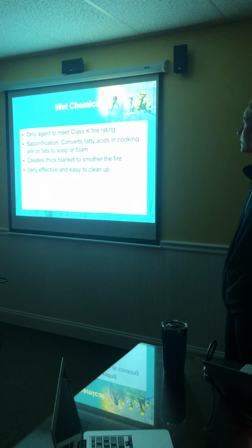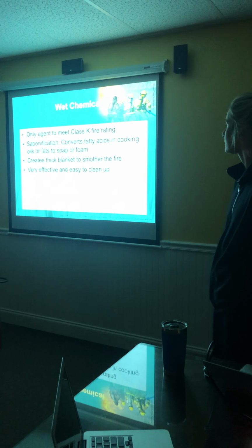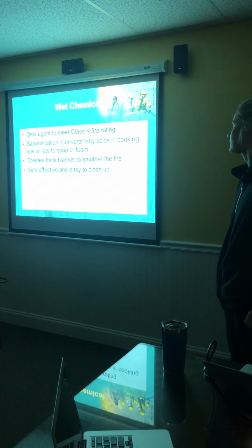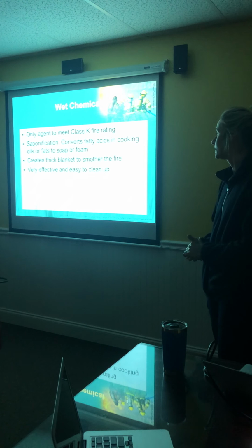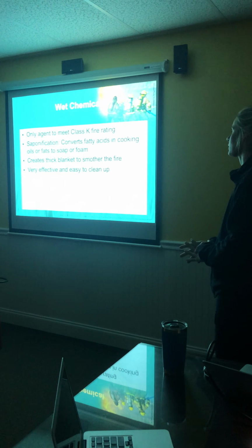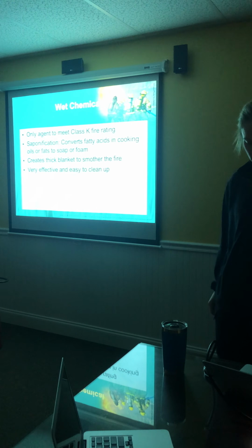Wet chemicals: the only agents to meet Class K fire rating. Saponification converts fatty acids in cooking oils or fats to soap or foam. It creates a thick blanket to smother the fire. It's very effective and easy to clean up.